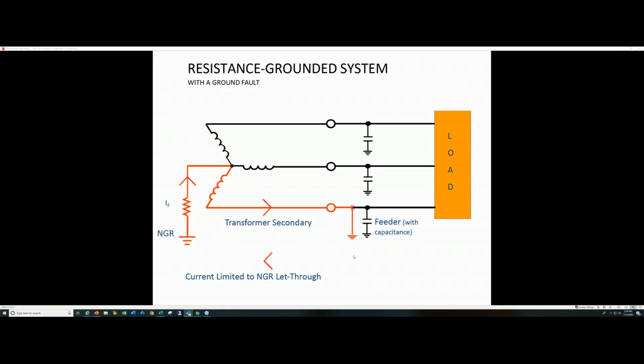So if we have a fault, let's say it's just a little heater or a three-phase motor or something, previous to HRG installations, we would have low voltage power circuit breakers trip off. And then that would cause some incidental piece of equipment that was important that was interlocked to the machine and shut the whole machine down. So we've had several incidences where this has actually saved the machine till we had the ability to shut down on an outage scheduled within a very short period of time and then fix what we had without interruption to the operation and without anybody getting hurt.